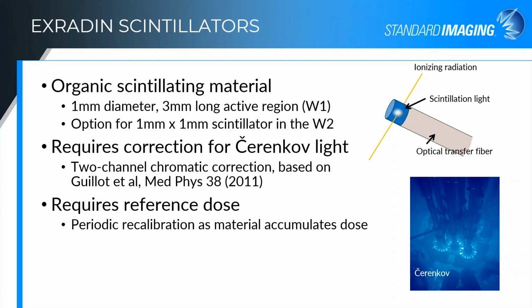We apply a 2-channel chromatic correction based on a publication from Mathieu Guillot et al. back in 2011. And that's what really enabled this to become an easily used commercial device. You do also have to give the scintillation detector a known dose if you want your output in terms of dose. It does have a fairly stable output, but because of the damage to the plastics, you do have to recalibrate periodically as the detector accumulates dose.